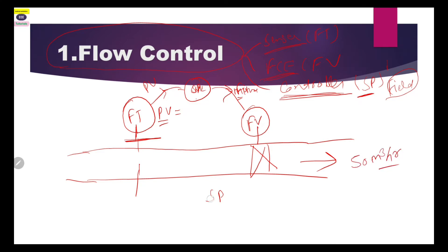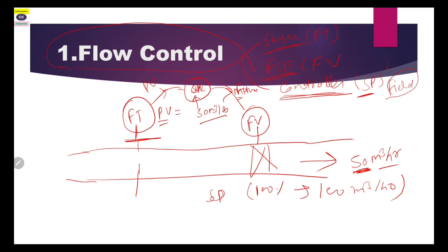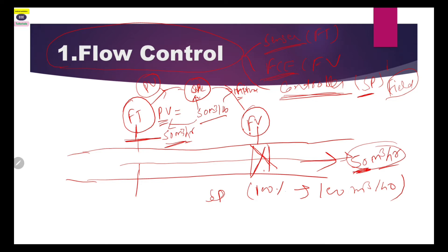Suppose we want the flow through this line to be 50 cubic meters per hour. If the control valve opens 100 percent, it will give 100 cubic meters. So we have given 50 cubic meters as the set value to the controller. The controller monitors the PV value, and when PV matches the set value, it will open the valve so that the flow in this line is 50 cubic meters per hour as required by the operator. This is the flow control strategy used in oil and gas.